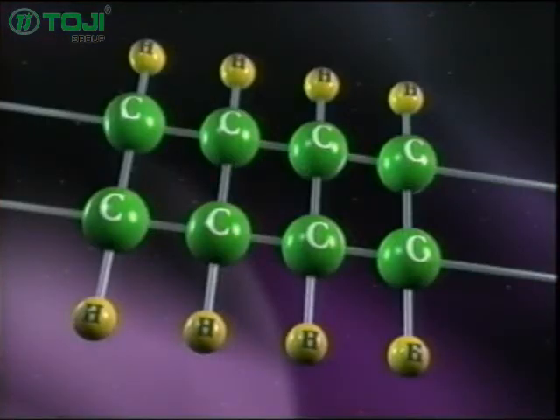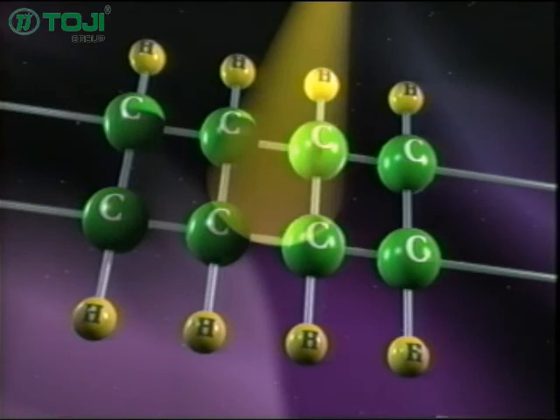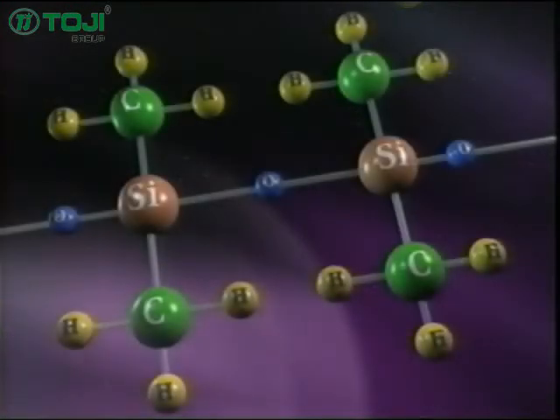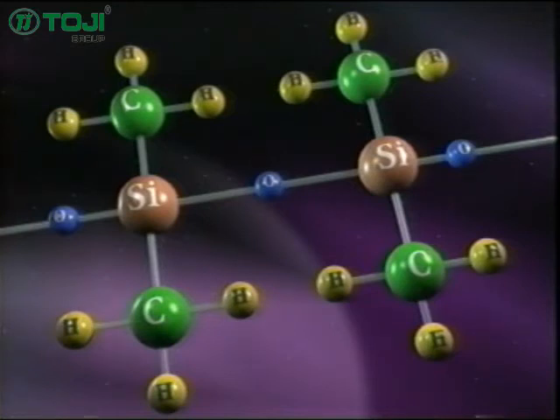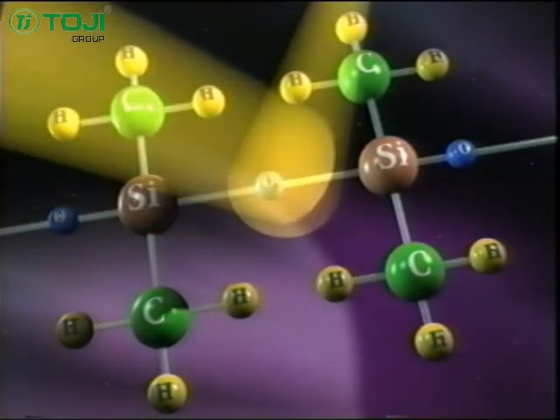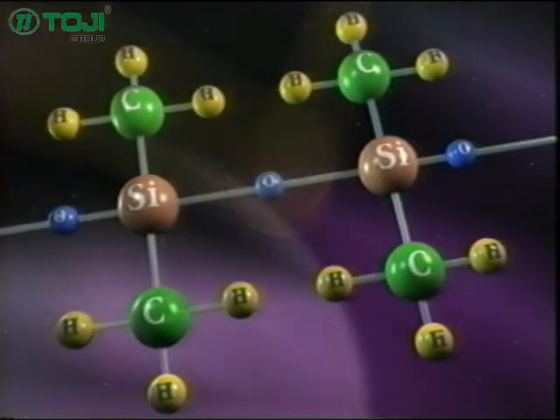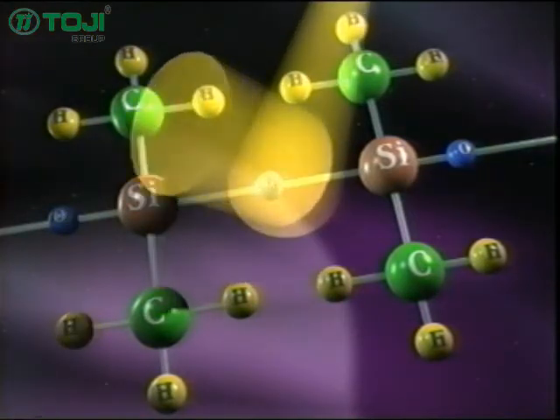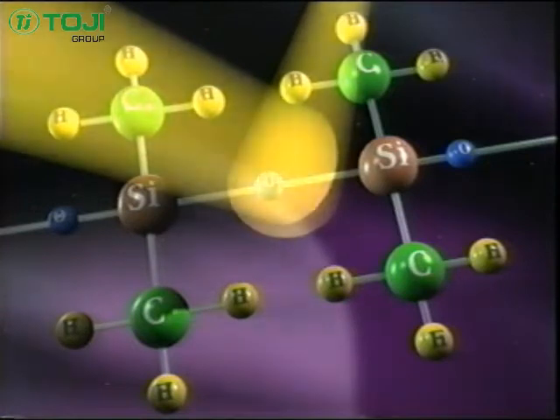The other harmful environmental factor is ultraviolet light. UV breaks down most carbon-based or organic materials like those found in EPR rubber or heat shrink terminations. Silicon to oxygen, not carbon to carbon, is the backbone of the molecular structure of silicone rubber, used in 3M Quick Term 2 termination kits. The silicon to oxygen bond is stronger than the destructive energy of ultraviolet light and is not prone to the surface crazing and cracking that affect EPR rubber and heat shrink termination products.